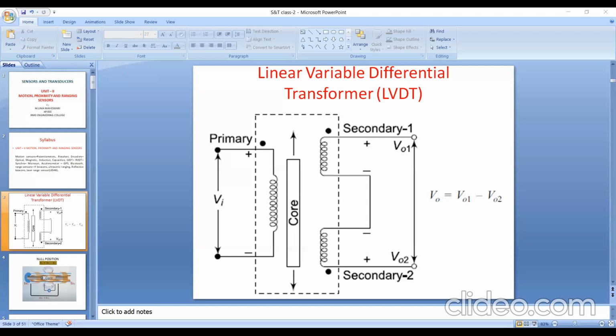Advantages of the LVDT. It is used for different applications, and there is a linear relationship. It has high sensitivity and high resolution, and the readings have good repeatability. The LVDT consumes less power, produces low hysteresis, and the frictional losses are very low. Whereas it has some disadvantages. It requires a large displacement to get a considerable differential output, and it is sensitive to stray magnetic fields and requires shielding. Temperature and vibration affect the output of the transducer, and the dynamic response is controlled mechanically. These are the disadvantages of the LVDT.